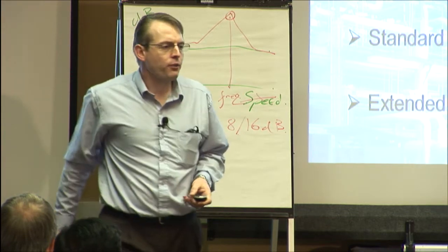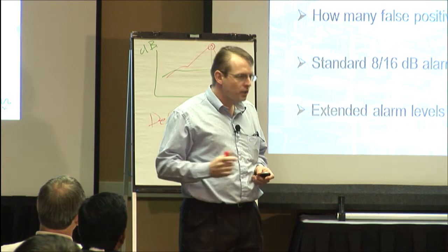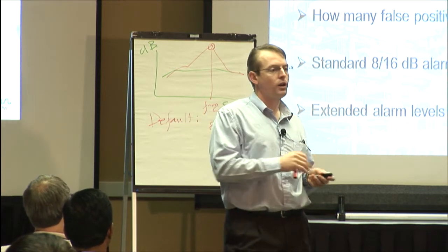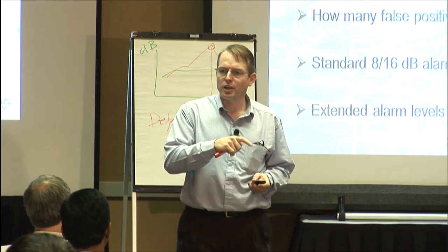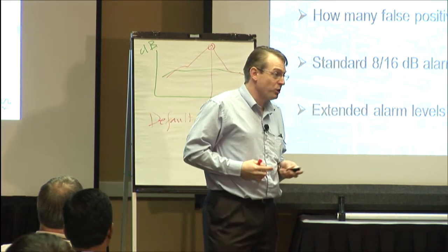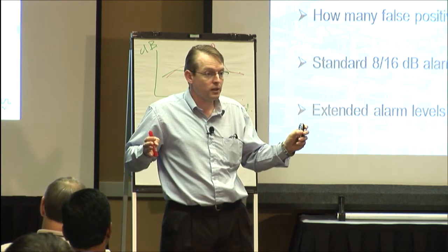Okay, so if we've done our test and unknowingly it's running a little faster, what's going to happen to the dB? It's going to go up a little, right? Okay, so potentially we're going to have a false positive result in terms of hitting a lubrication alarm or a failure alarm, correct? Okay, but if your kit's critical, you're going to prefer that to missing something, right? Now, if the piece of kit's not so critical, what are you going to do? You don't want to be lubricating everything, okay? Especially if you've got a bigger band of dB that piece of kit operates over, depending on the speed, okay?